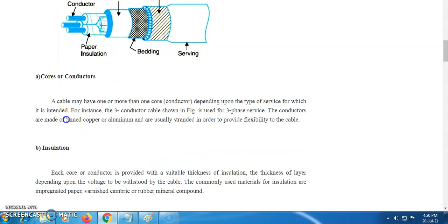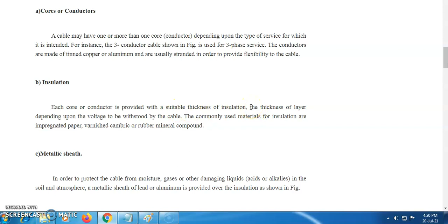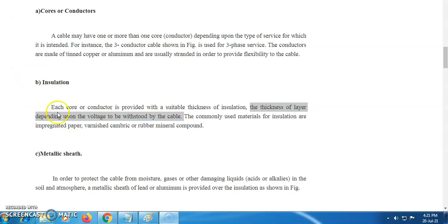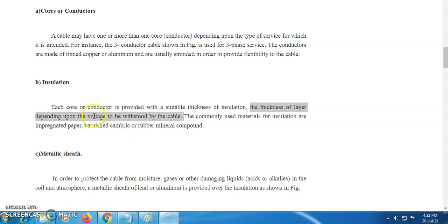This is the conductor which is made up of either copper or aluminum, tinned copper or aluminum, right? The insulation, second, is paper insulation. Each core conductor is provided with a suitable thickness of insulation. The main thing you need to understand is the thickness of the layer depends upon the voltage to be withstood by the cable. We don't design the insulation for the current rating. You need to design the insulation for the voltage. That is very important. So as I told, the thickness of the insulation layer provided on the conductor in the cable depends upon the voltage. So that is very important.